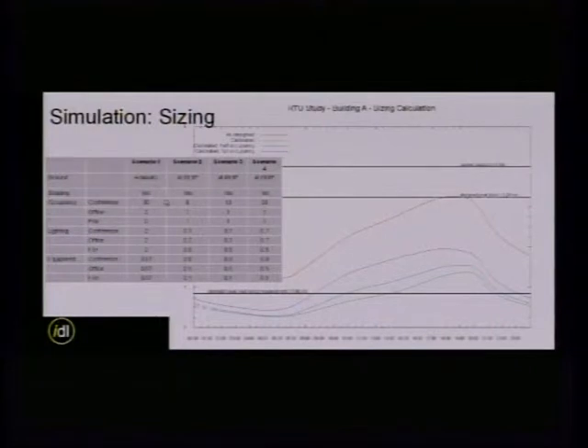Now scenarios two, three, and four simply add the floor heat loss and change the occupants of the conference room. So it's not 20, but 5, 10, and 20. The difference between scenario 1 and 4 is exactly the same except for the floor heat loss. Then we run it. As designed, scenario 1 is exactly the same. It doesn't matter if you use a simulation tool, EnergyPlus for example, which I used for this, or the CLTD spreadsheet. You should come up with exactly the same thing right there.